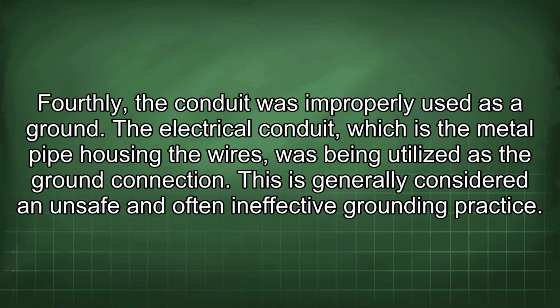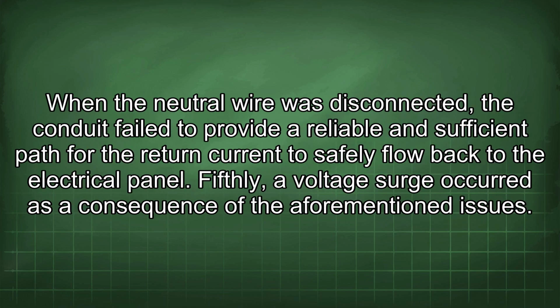Fourthly, the conduit was improperly used as a ground. The electrical conduit, which is the metal pipe housing the wires, was being utilized as the ground connection. This is generally considered an unsafe and often ineffective grounding practice. When the neutral wire was disconnected, the conduit failed to provide a reliable and sufficient path for the return current to safely flow back to the electrical panel.